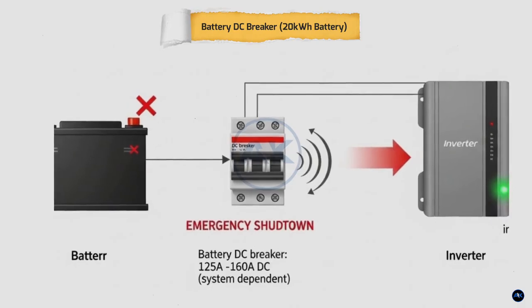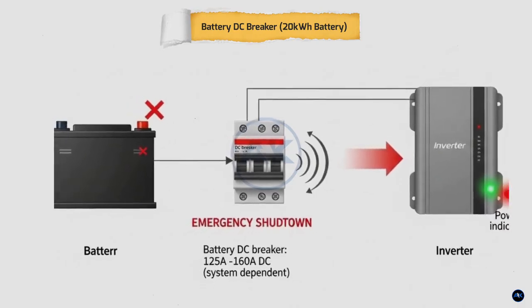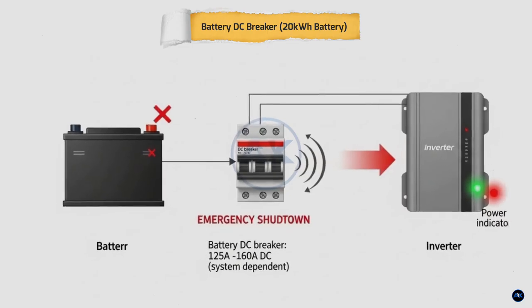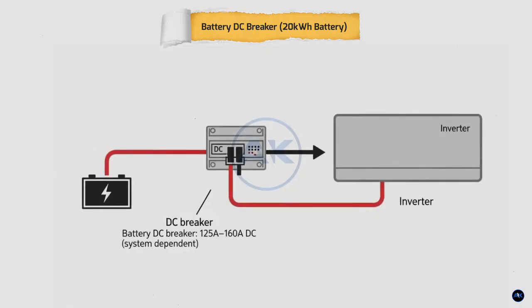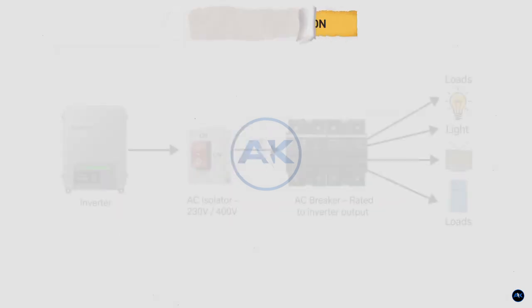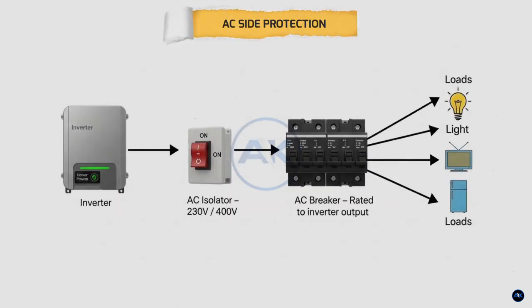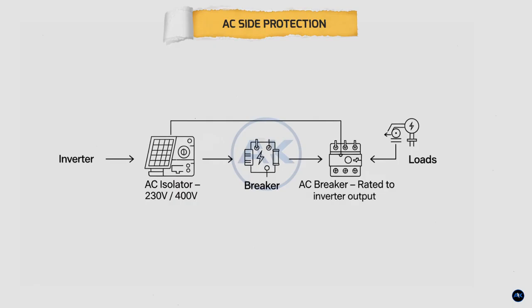Battery DC breaker, 20 kilowatt-hour battery. Your battery bank needs its own DC circuit breaker. For a 20 kilowatt-hour battery on a 12 kilowatt inverter, use a properly rated breaker capable of handling high DC current. AC side protection. AC isolator and main AC circuit breaker. On the AC side, an AC isolator allows safe inverter shutdown. A main AC circuit breaker protects against overloads and short circuits.